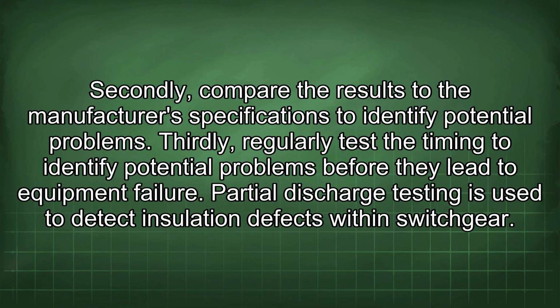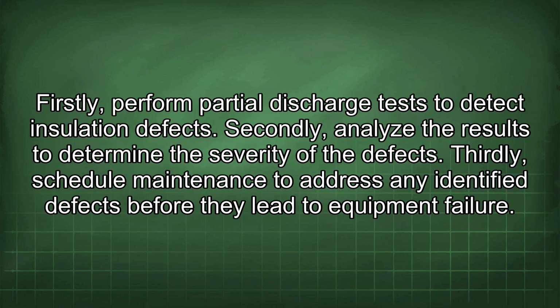Partial discharge testing is used to detect insulation defects within switchgear. Firstly, perform partial discharge tests to detect insulation defects. Secondly, analyze the results to determine the severity of the defects. Thirdly, schedule maintenance to address any identified defects before they lead to equipment failure.